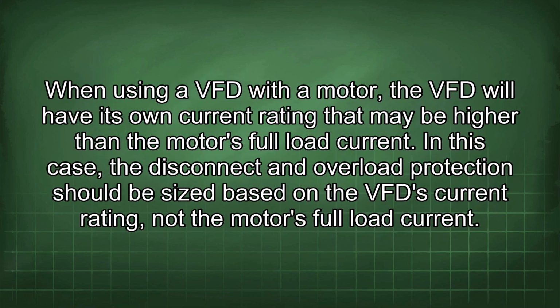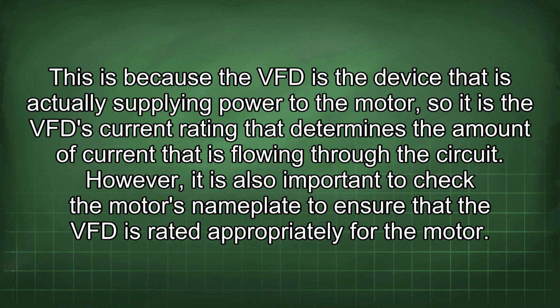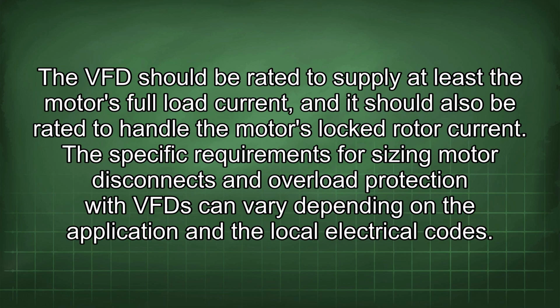When using a VFD with a motor, the VFD will have its own current rating that may be higher than the motor's full load current. In this case, the disconnect and overload protection should be sized based on the VFD current rating, not the motor's full load current. This is because the VFD is the device that is actually supplying power to the motor, so it is the VFD current rating that determines the amount of current that is flowing through the circuit. However, it is also important to check the motor's nameplate to ensure that the VFD is rated appropriately for the motor. The VFD should be rated to supply at least the motor's full load current, and it should also be rated to handle the motor's locked rotor current.